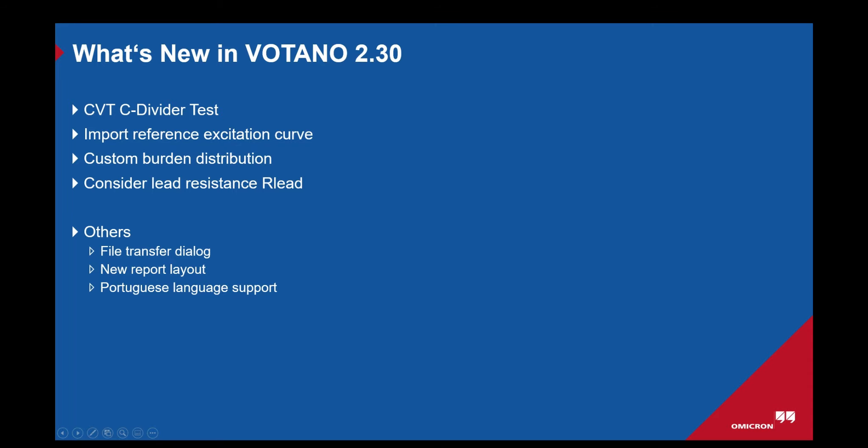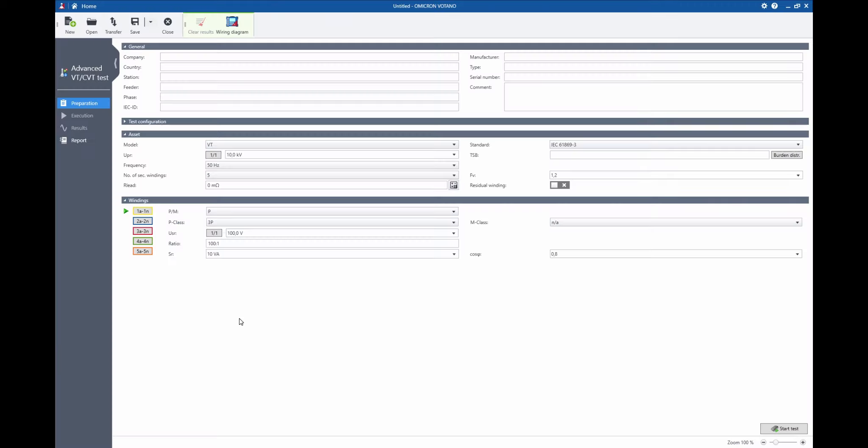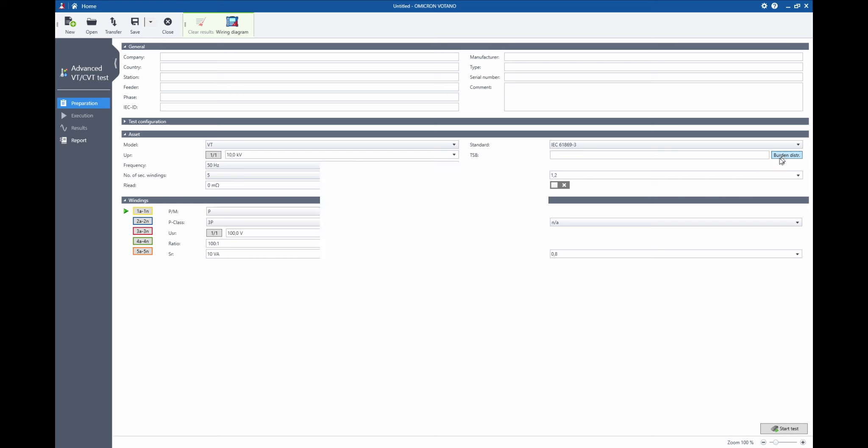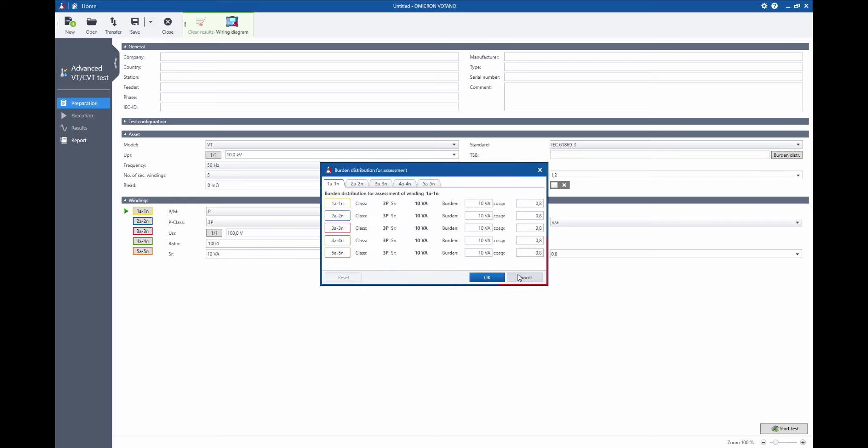The next feature on our list is the custom burden distribution. This feature is available in the advanced VT and CVT test and it's located right here. Here it's possible to set the burden distribution for assessment for each of the windings separately.